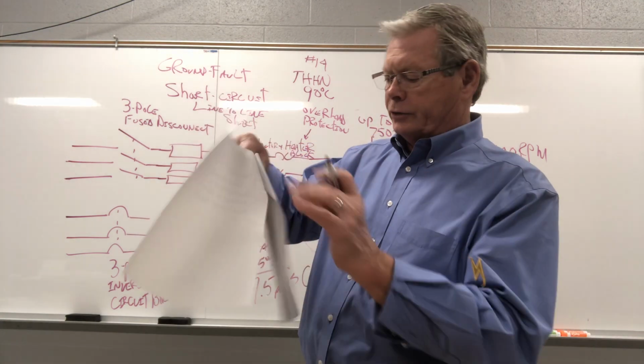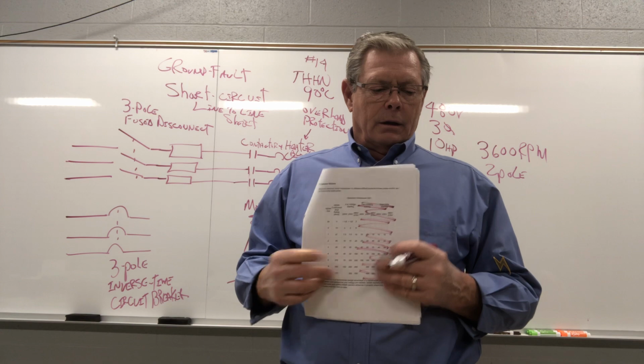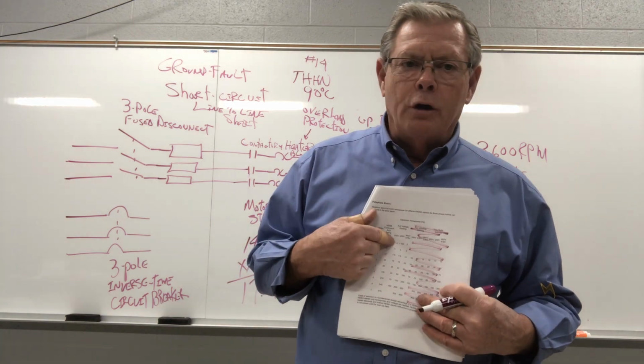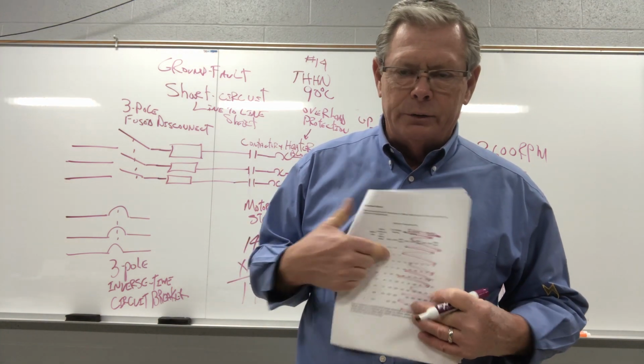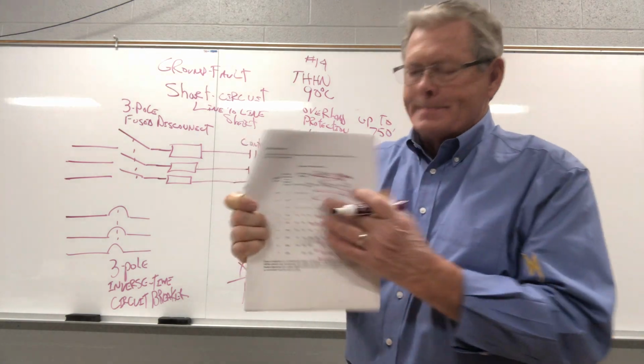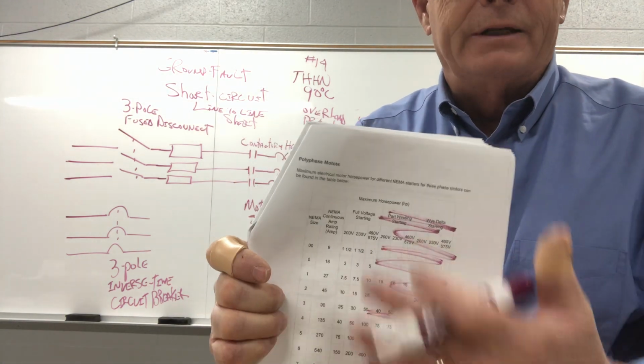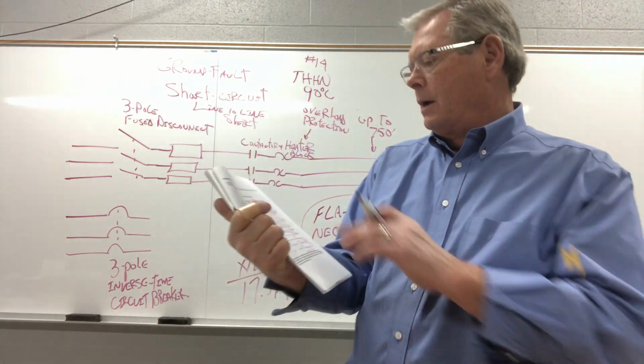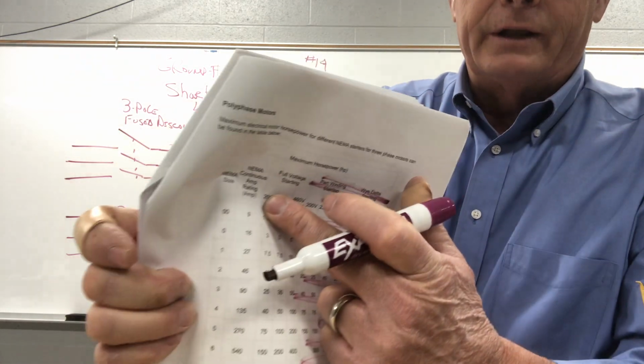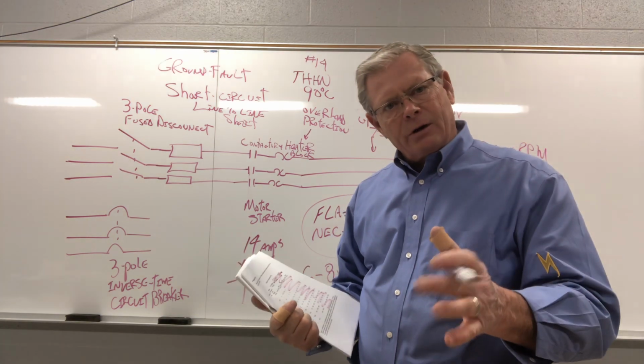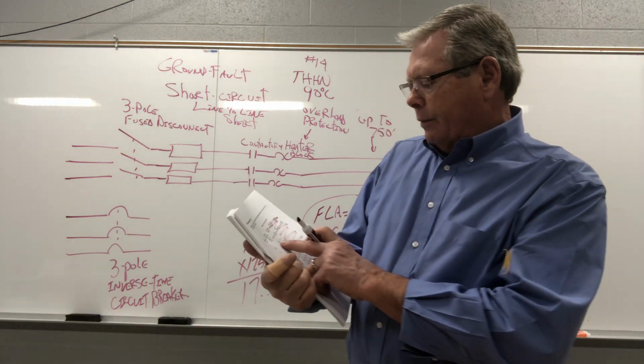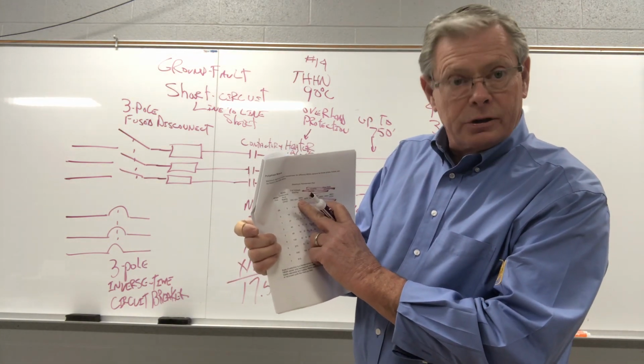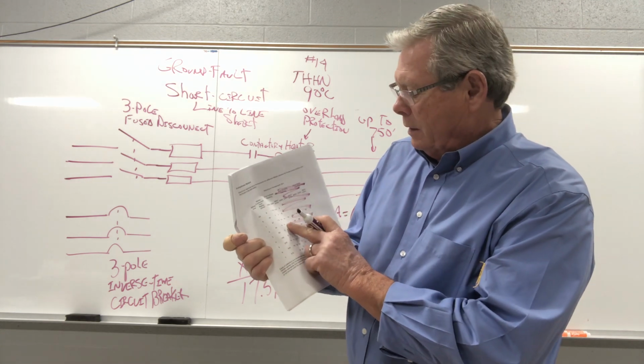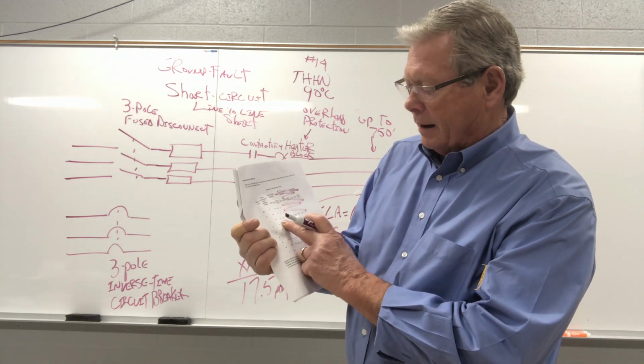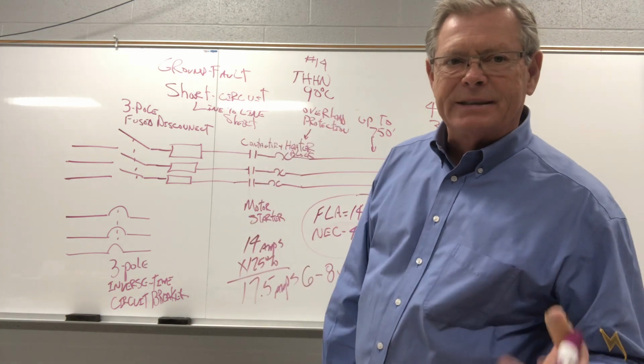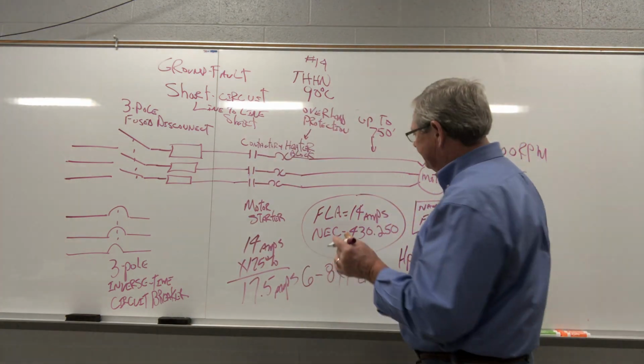Now, on a starter, you have to go by horsepower at the application voltage. So this side here, you don't need, that's why I marked it out. You just need this side here. You need full voltage starting. That's what we're doing. It's called across the line start or full voltage start. If we take 460, it's close enough to 480, right? Go down to 10 horsepower, and across here, it's a NEMA size 1 starter, okay?